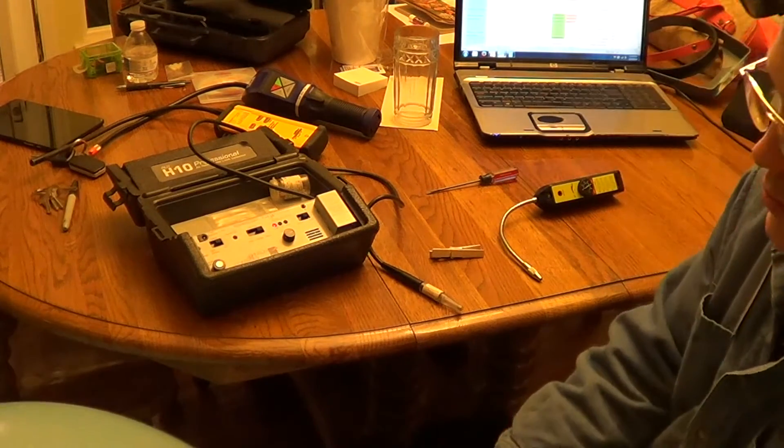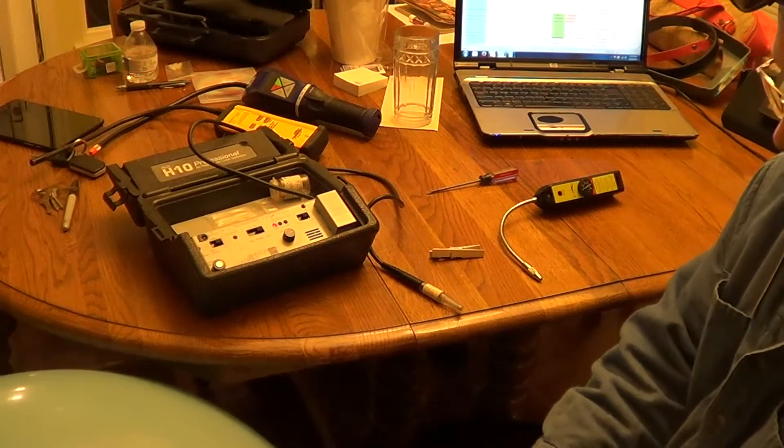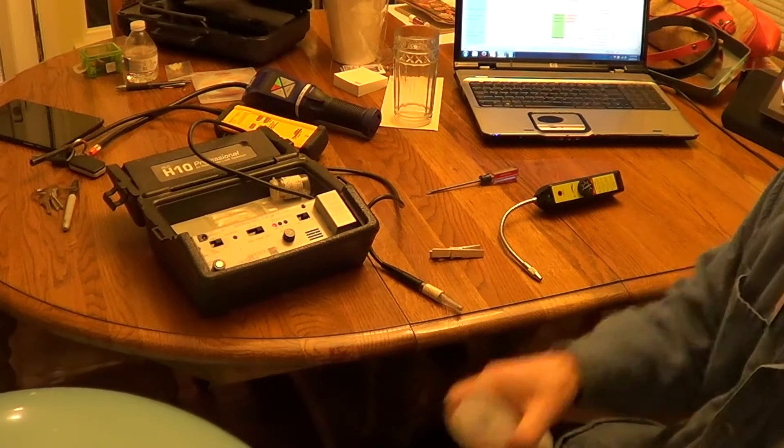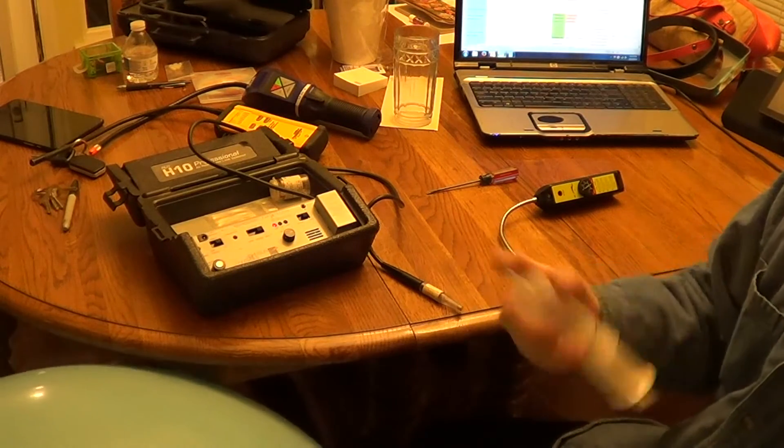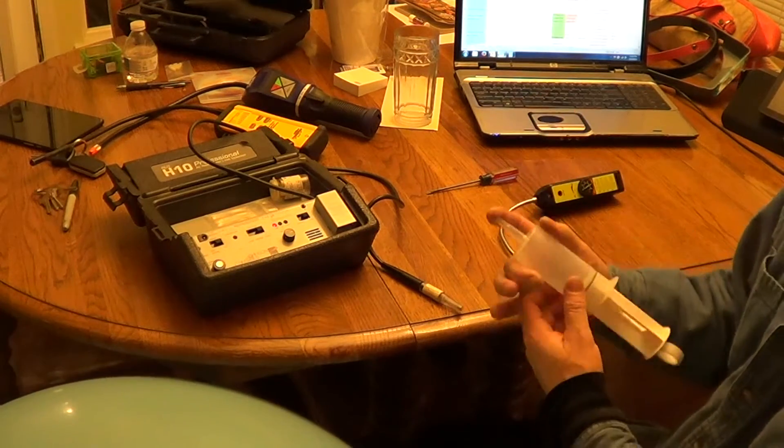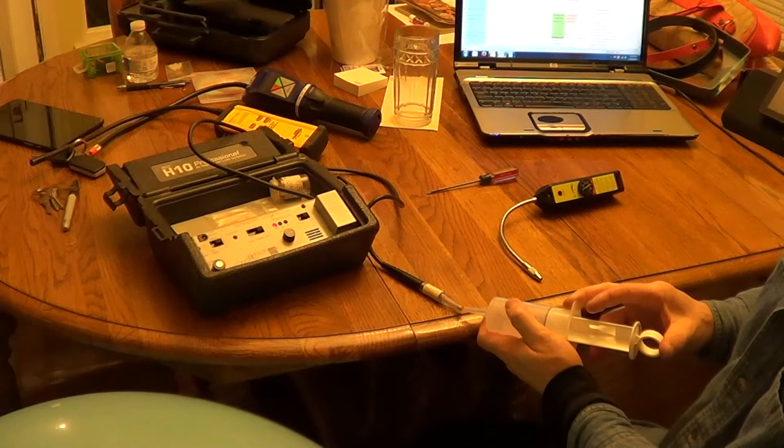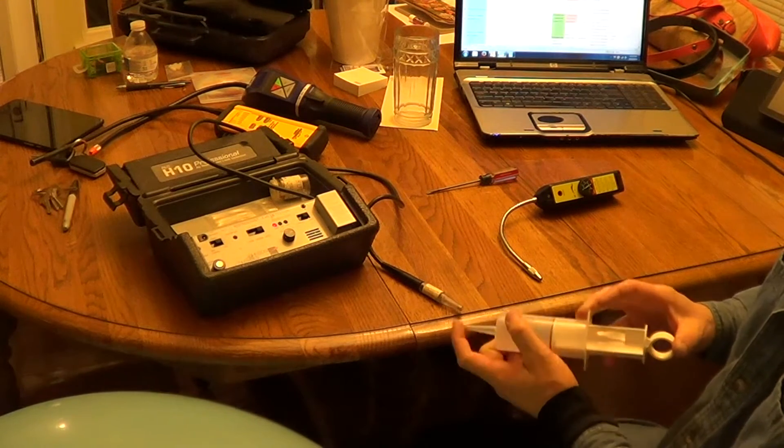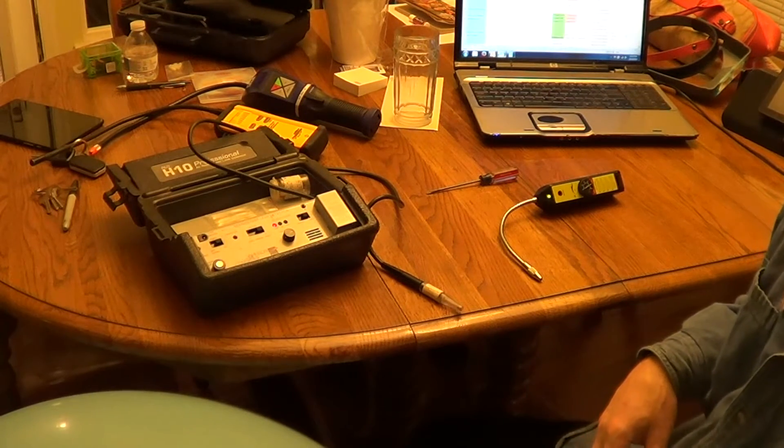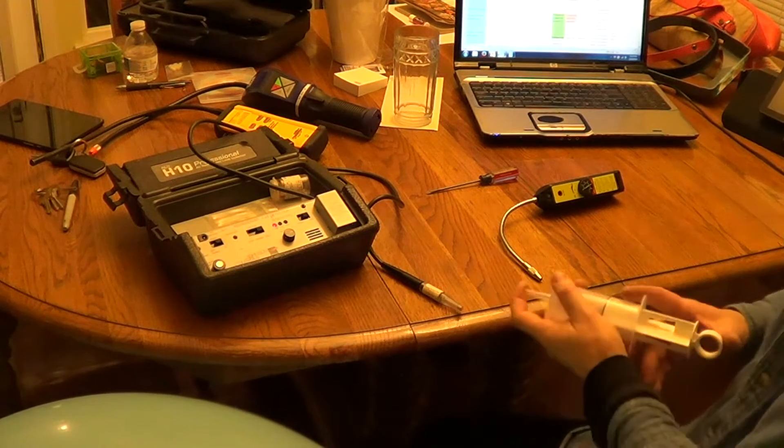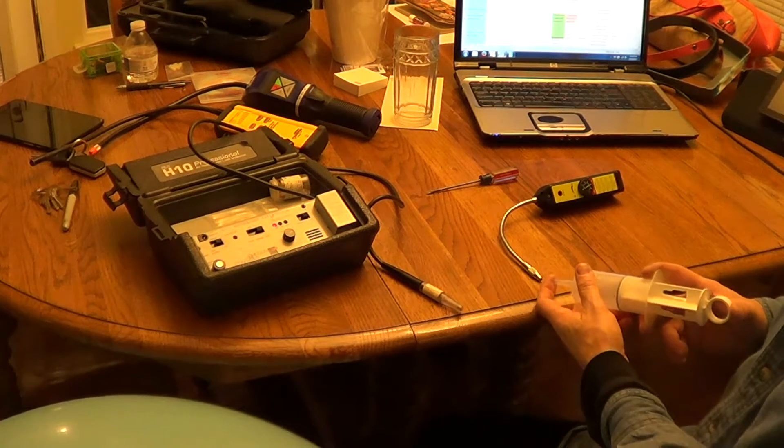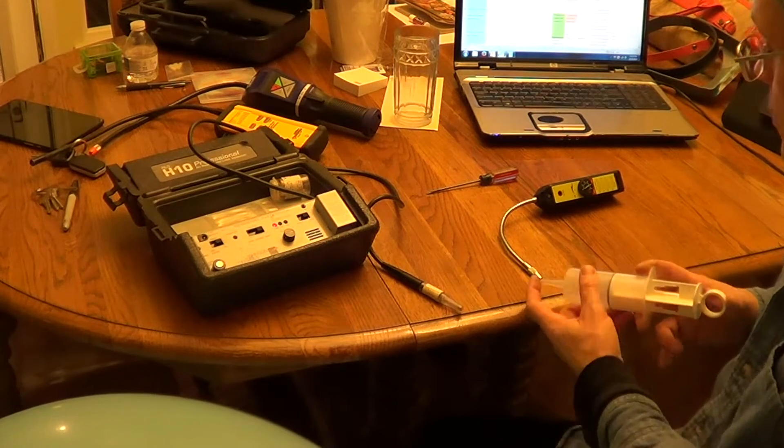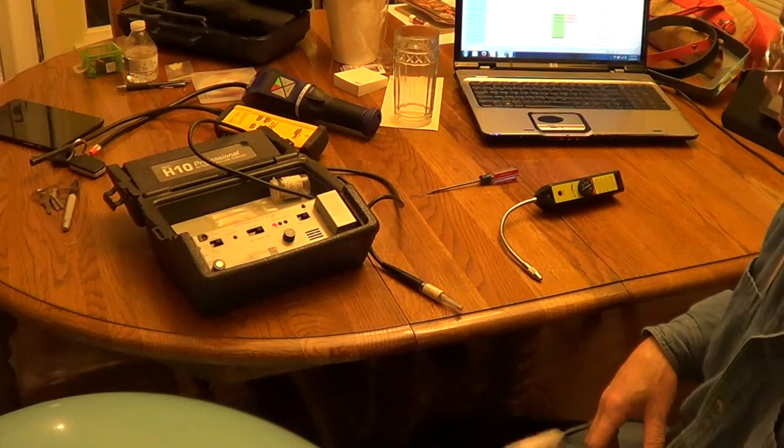So I'm filling up 50 cc, fill the rest with air, so I got five parts per million R410A blend. H10 barely picks it up as a really small hit at five parts per million. Chinese twenty dollar leak detector quite easily picks it up.